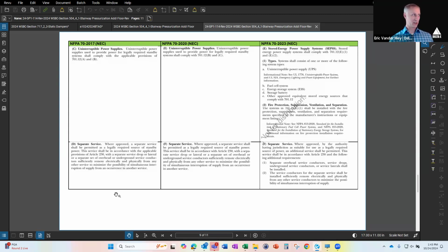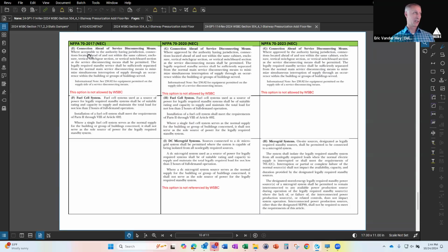Then you have the separate service section, which was D, F, and then still F, though there has been some editorial revisions as far as how that is presented. The connection ahead of the service disconnect main, the one that hasn't been allowed for the stairway pressurization systems per the Washington State language, was E, then it became G, it's currently G. As I mentioned, fuel cells now doesn't have its own section, and then the microgrid system has been revised also.